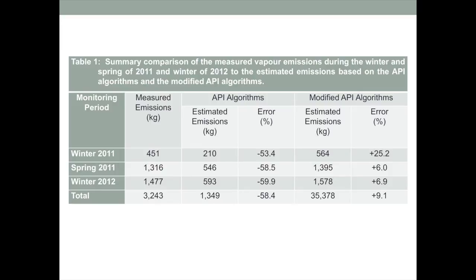The data from the rest of the monitoring showed we had continuous monitoring throughout the spring of 2011, some sensor and panel problems over the summer, and then better data again into 2012. With those larger data sets, we got much better results. Instead of being high by a factor of 25%, we're high by only 6%, and if you weight the results for the entire available time series, you wind up with an overestimate of about 9.1% — which, considering what we're trying to do and how we're estimating it, is still a pretty good number.